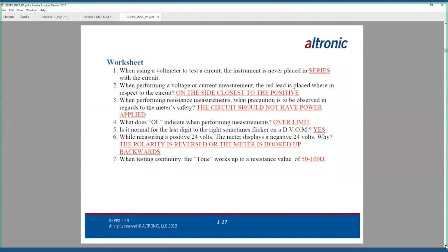When testing continuity, the tone works up to a resistance value of, now we hadn't covered this one, so this is a good thing. So the tone works up to 50 to 100 ohms, so it varies from one meter to the next. So again, if I'm just trying to figure out a pinout between one end of a harness to the other end of a harness, the continuity test is good because I'm not expecting to see 50 ohms, more than likely much less than 4 ohms on just a wire, whether it's 5 foot long or 50 feet long. Any questions before we advance to the next part?